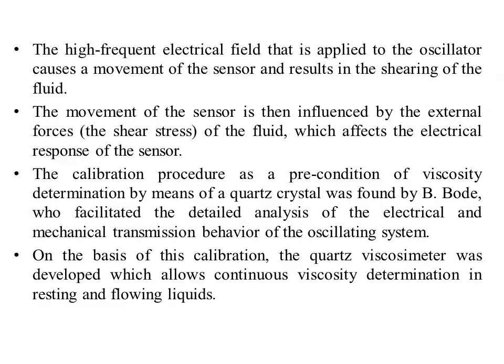The quartz crystal vibrator or the viscometer. The high frequency electrical field that is applied to the oscillator causes a movement of the sensor and results in the shearing of the liquid. The movement of the sensor is then influenced by the external forces, that is the shear stress of the fluid, which affects the electrical response of the sensor.